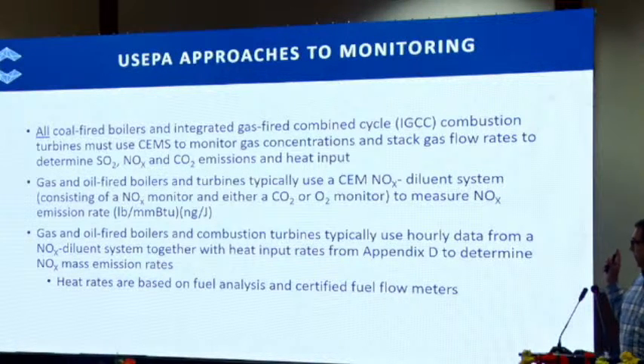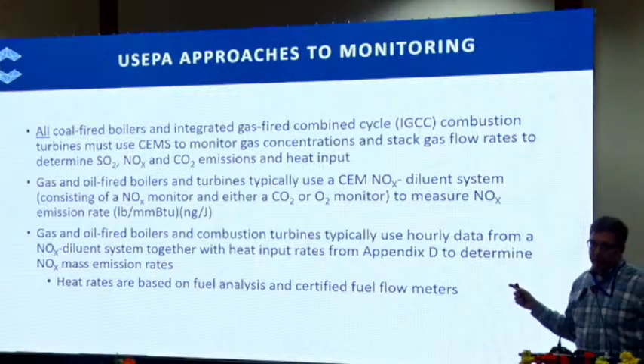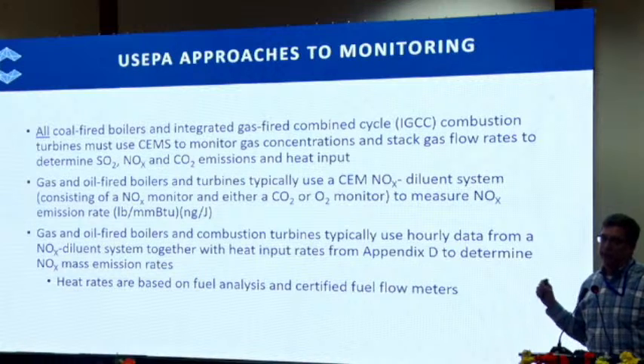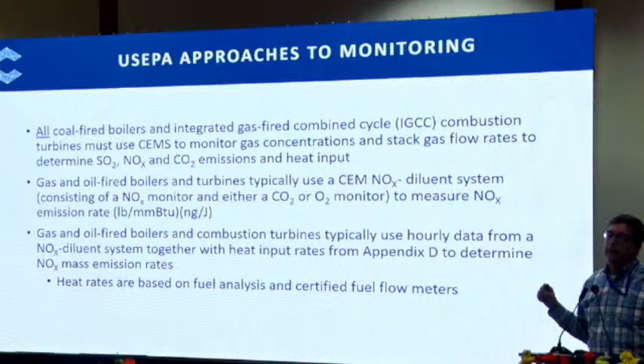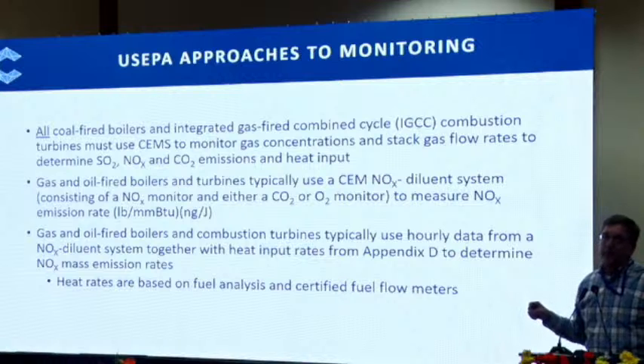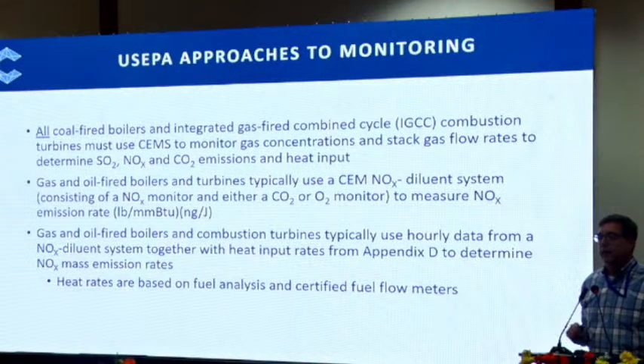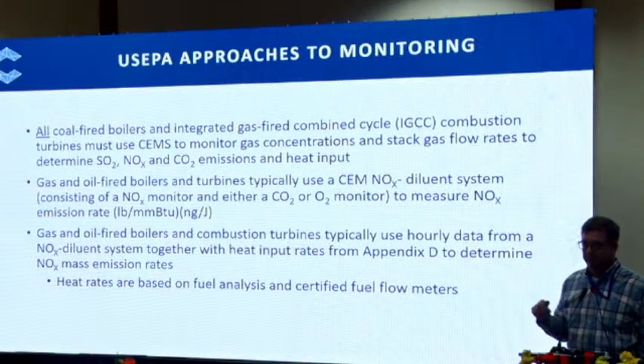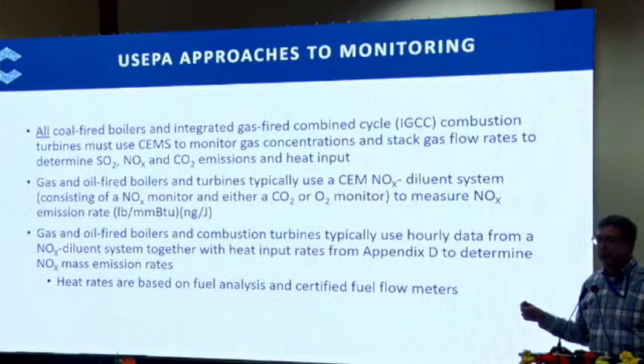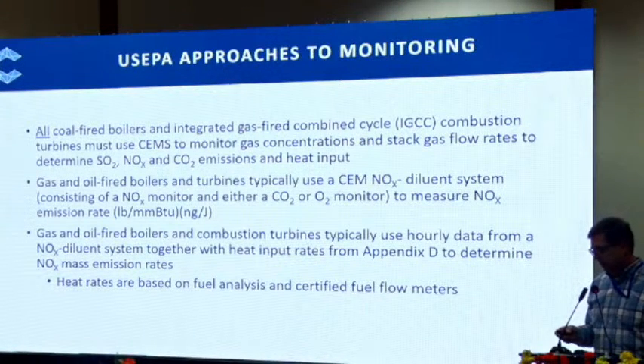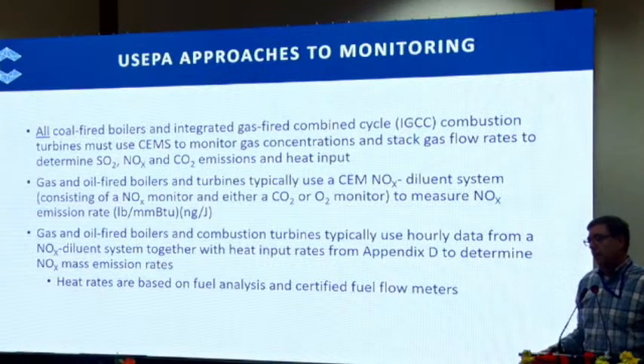So for combustion turbines, you do not have to have a flow monitoring system. You can use the fuel flow rate and a certified fuel flow meter. You take that fuel flow rate and the gas analysis, which gives you a caloric value or a higher heating value, and you can calculate your mass emissions of the pollutants that way.